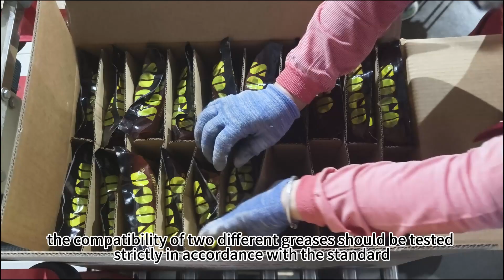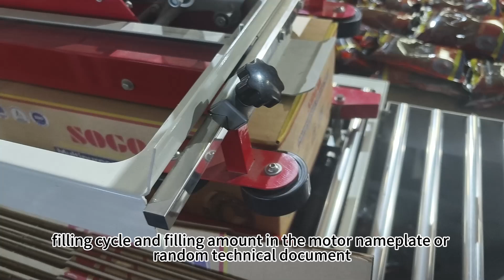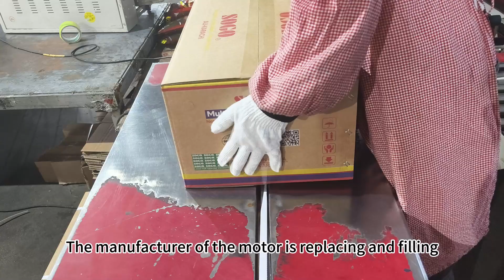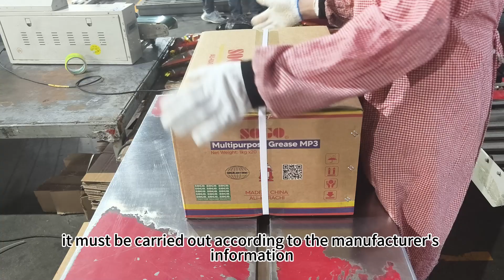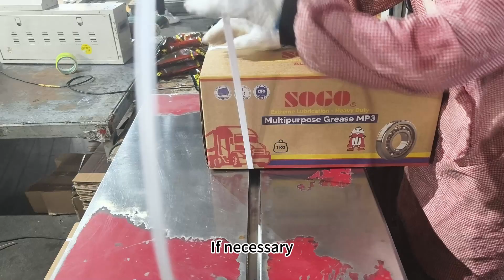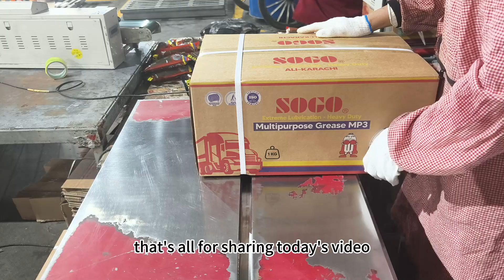In order to avoid similar problems, motor manufacturers should specify the specific brand number of grease, filling cycle, and filling amount in the motor nameplate or accompanying technical documents. When replacing and filling grease, it must be carried out according to the manufacturer's information. If necessary, all the old oil should be discharged and the new oil should be added after cleaning.